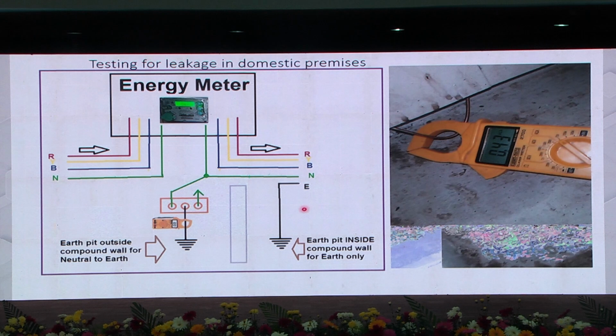So, based on this, what have we done? We have done this in an installation. This is the point of supply, and the neutral is connected. We have provided a meter to measure the current when our neutral is connected. See, for example, in this house, this neutral is connected to the supplier neutral. This is a TNS system. When this neutral is connected, even after switching off our home, we will have a leakage current. It is showing 0.43. See the video.